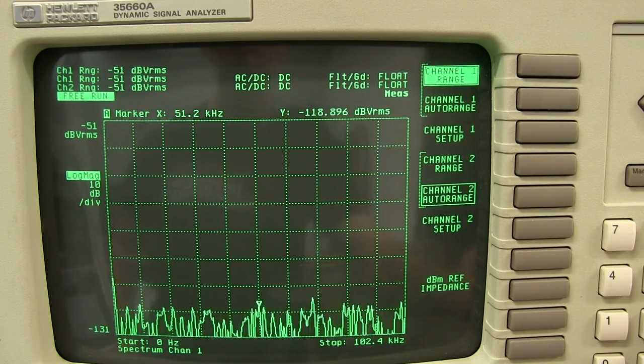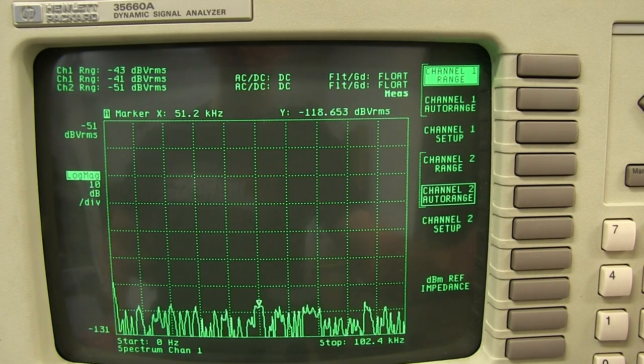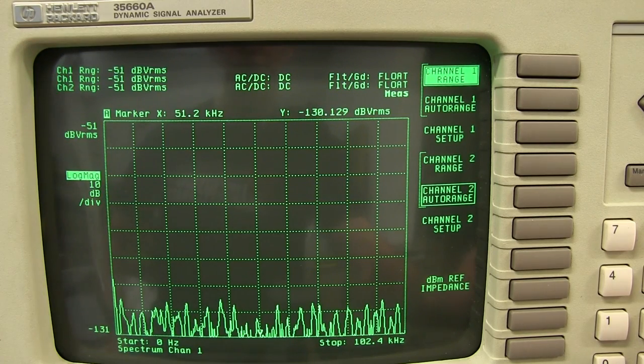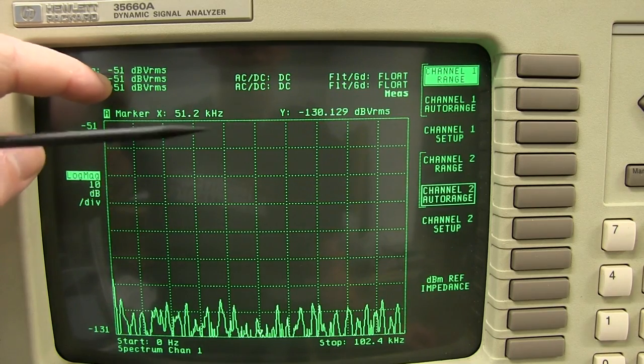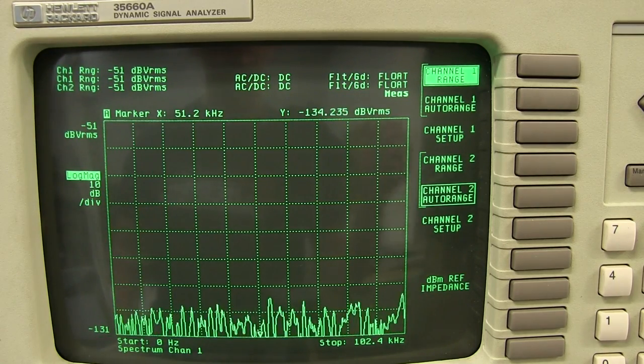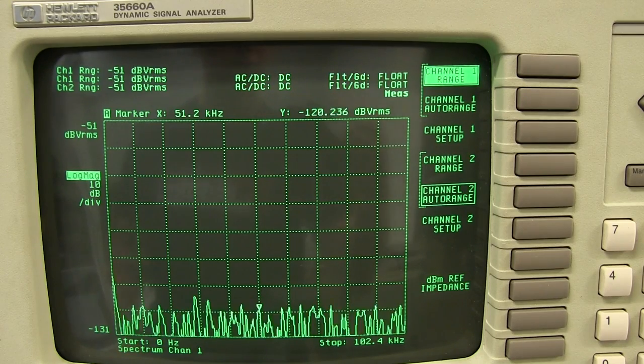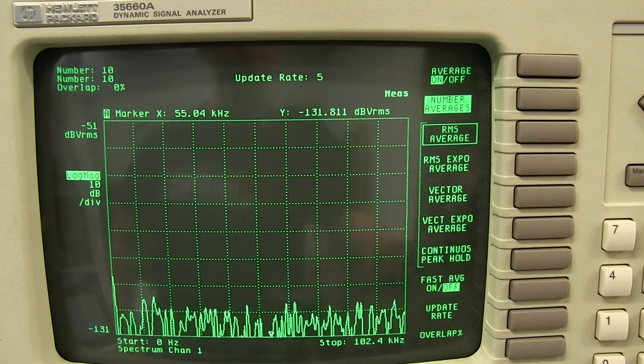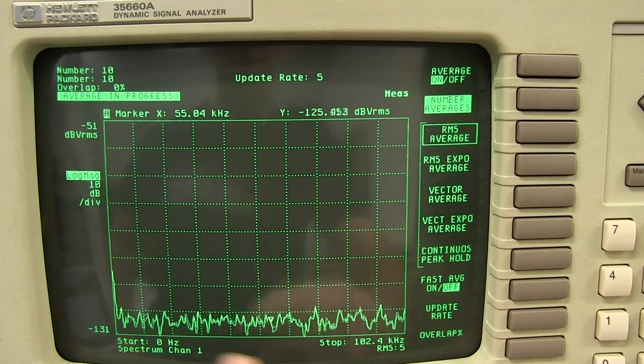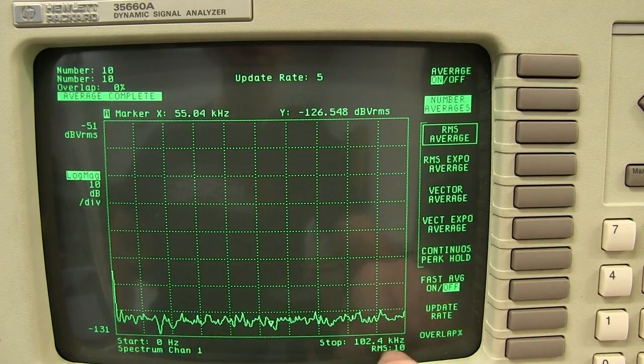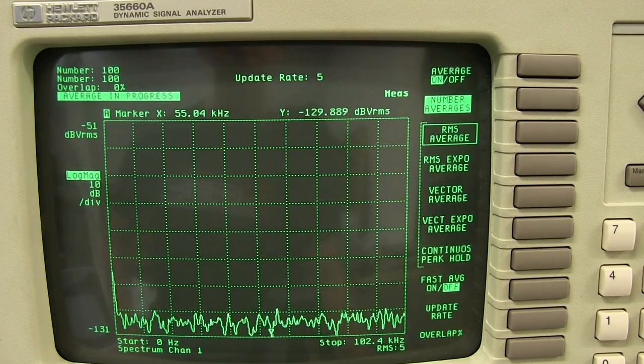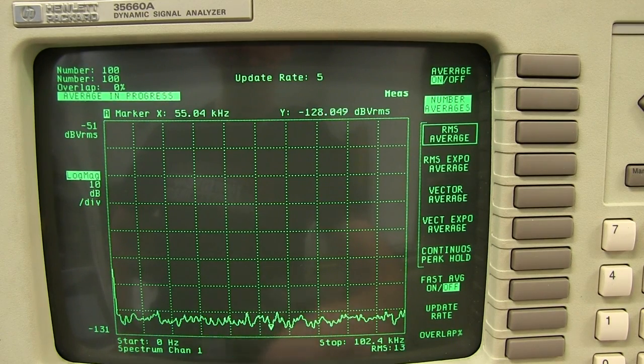Because we're measuring low signal levels, go to Input, select channel 1 range. At the moment it's auto-ranging — we really don't want that; we want it to be fixed. The highest gain range, or the lowest voltage range it's got, is minus 51 dB volts RMS, which is equivalent to about 4 millivolts peak or thereabouts. Next thing we want to do is turn on some averages — press the average button on the front, turn average on. I'm going to change the number of averages to 100. Now when you press start and begin acquisition, we're starting to get a bit of a plot already.